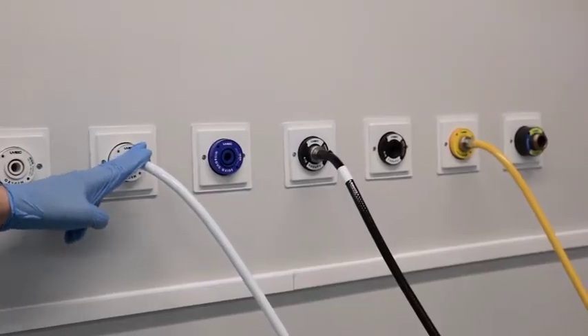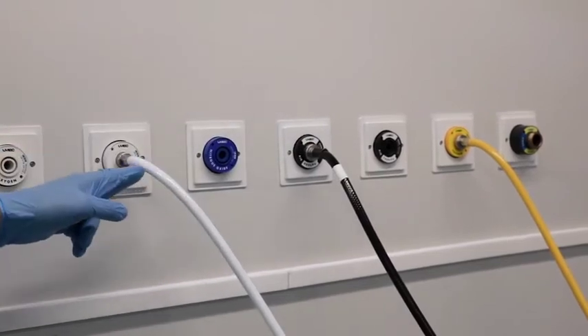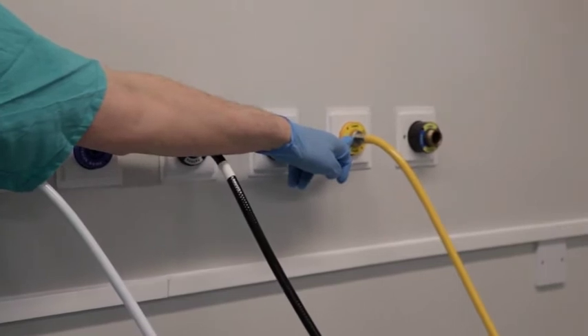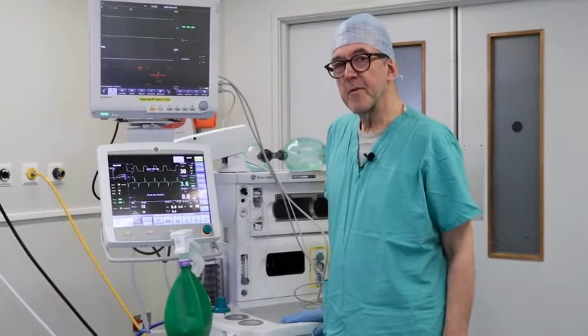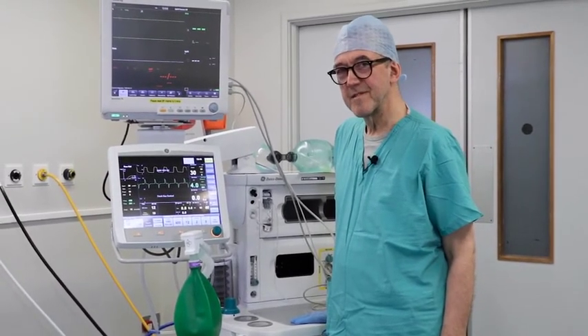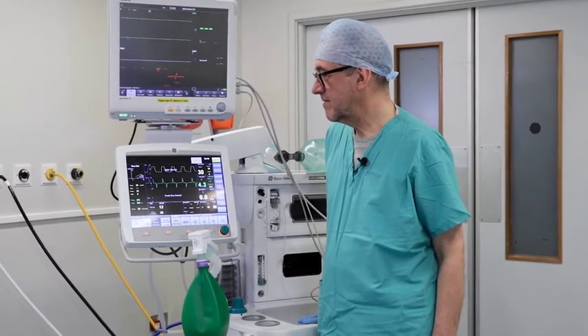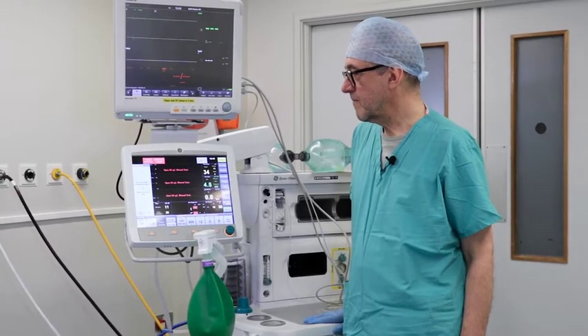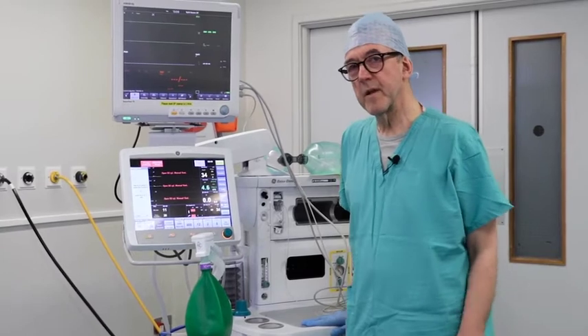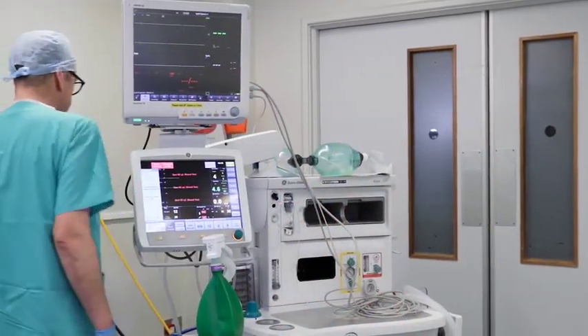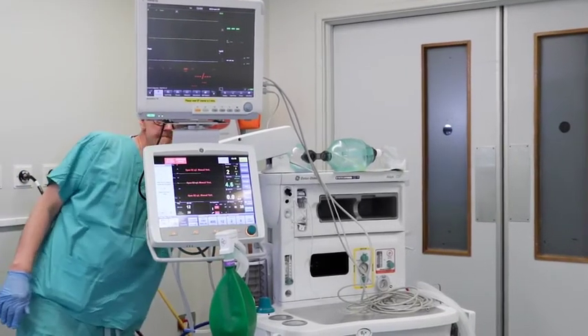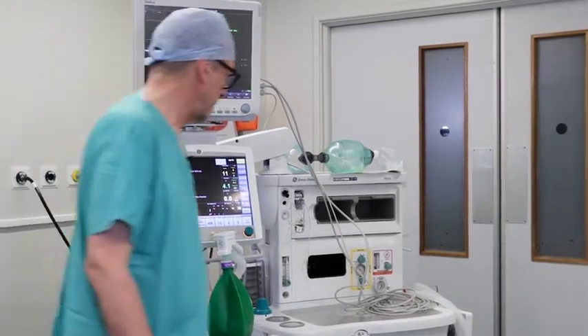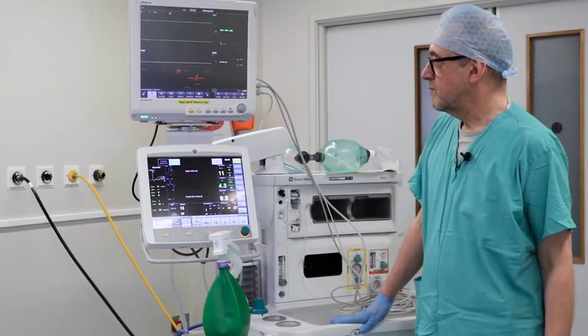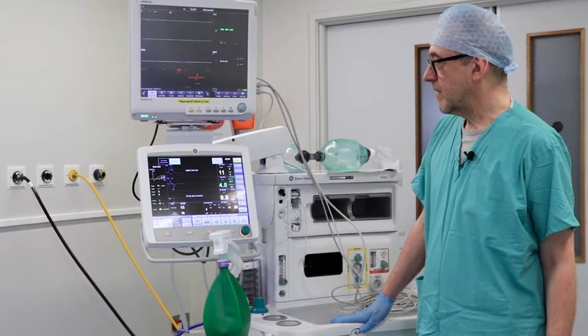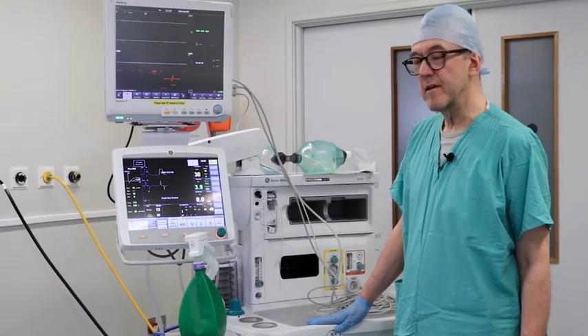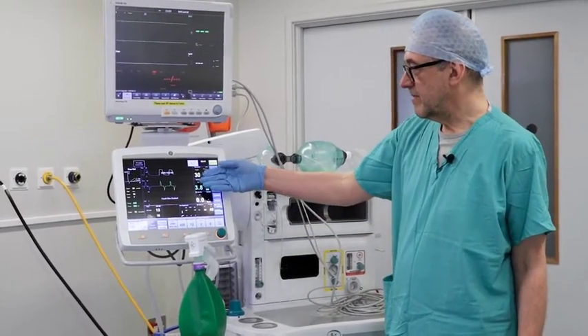The ventilator is driven by oxygen and air from the pipeline supply. Suction is also delivered from the wall pipeline. If the pipeline supply of oxygen fails, this is what will happen. The ventilator will still operate by opening the auxiliary oxygen cylinder, which is located at the back. The ventilator is now running on the oxygen supply from the cylinder at the back of the machine. Bellows are operating and ventilation has been resumed.